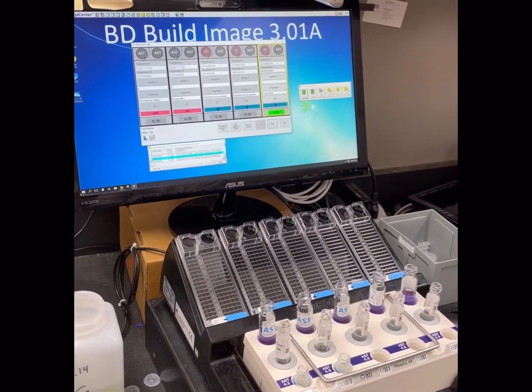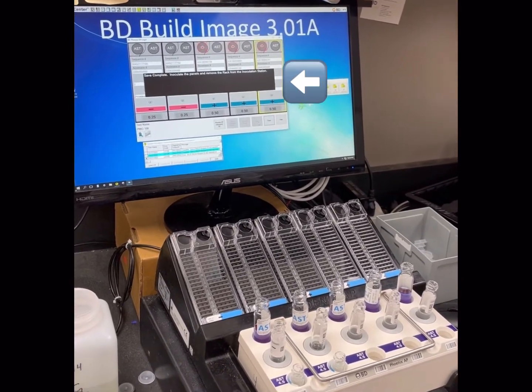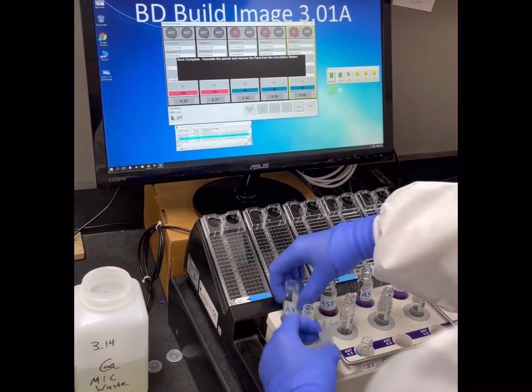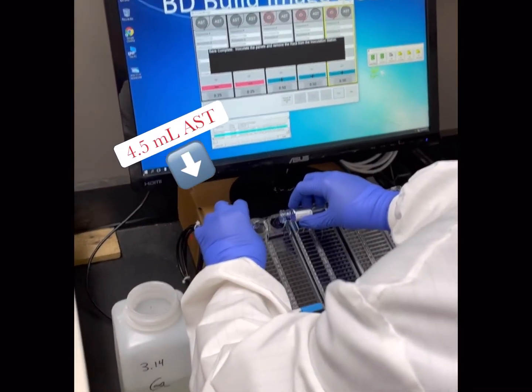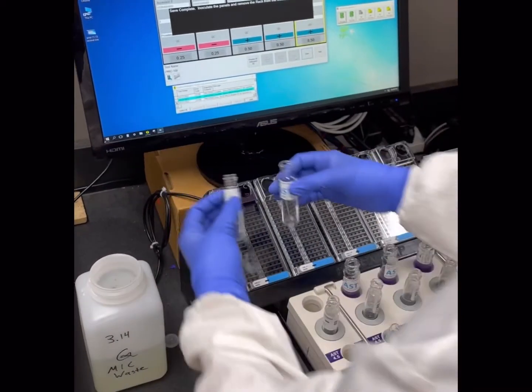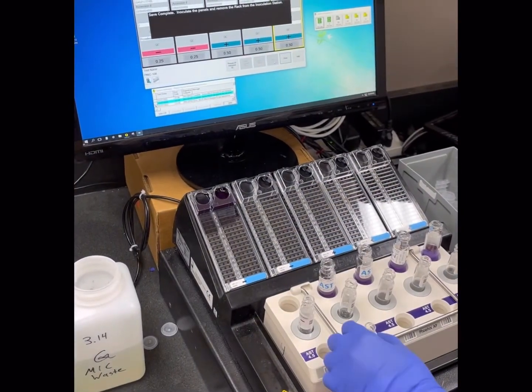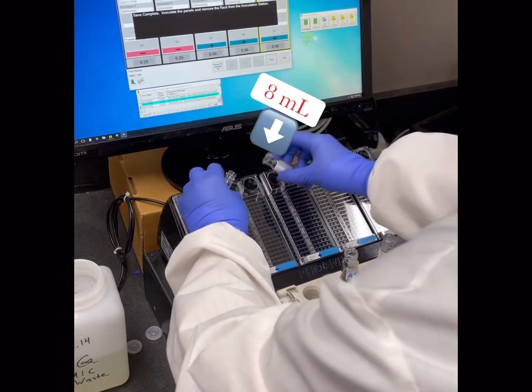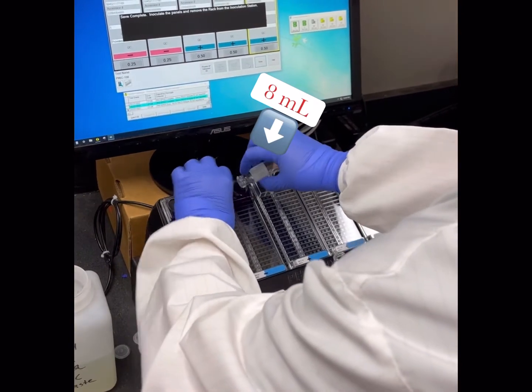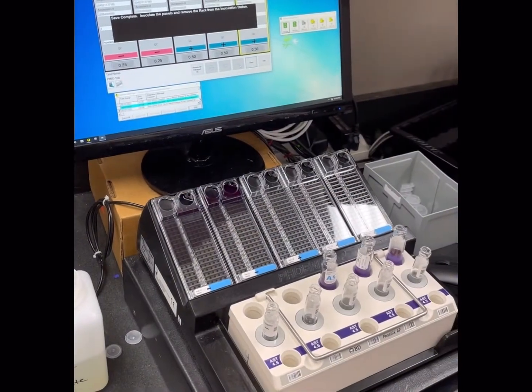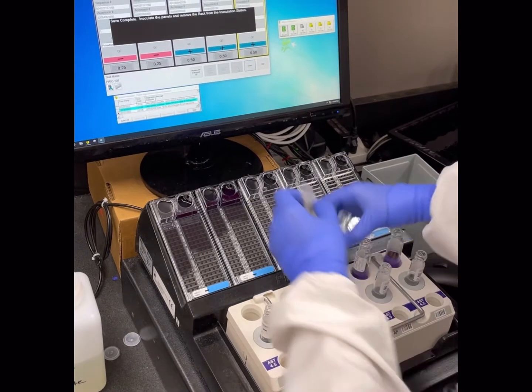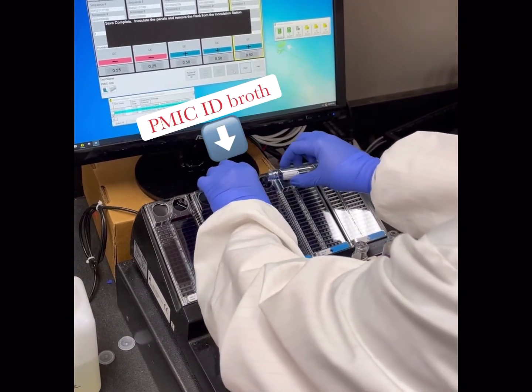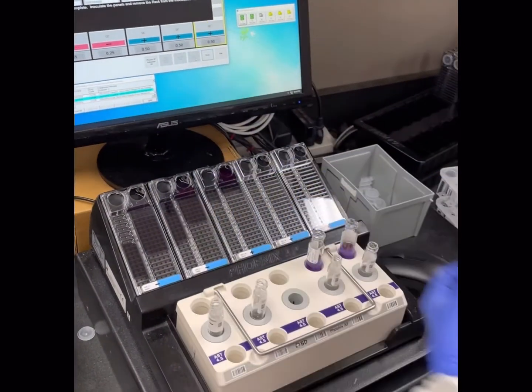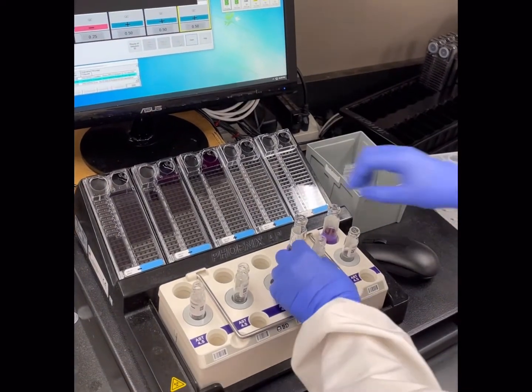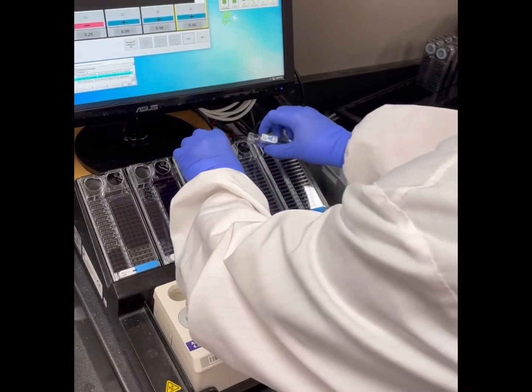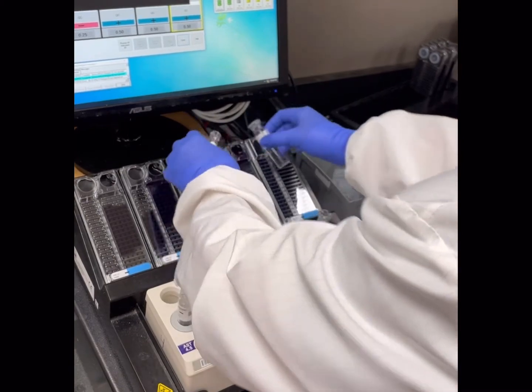When the panels have been saved, Save Complete will appear on the login screen. For the NMIC panels, the 4.5 milliliter AST broth is poured into the left side of the panel, which is narrower, and the 8 milliliter AST broth is poured into the right side. For PMIC panels, the ID broth is poured into the left side of the panel, which isn't necessary for the MIC, but cuts down on the amount of waste. The 8 milliliter AST broth is poured into the right side of the panel.